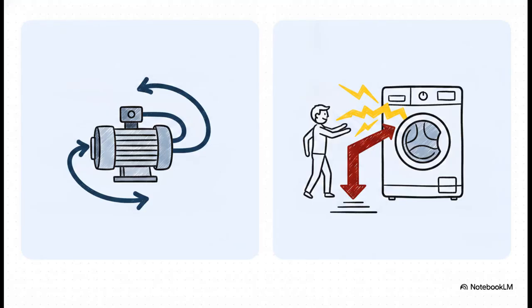All right, Section 1, the purpose of earthing, the escape route. Picture this. You're doing a normal load of laundry, but inside your metal washing machine, a live active wire has vibrated loose, and now it's directly touching the inside of the metal casing. So the outside of the washing machine is actually live. Let's contrast these two states. In normal operation, electricity flows safely through insulated cables, powers the motor, powers the pump, and returns nicely through the neutral wire. But in a fault condition, that rogue current is just sitting on the metal casing, waiting for a path to the earth.